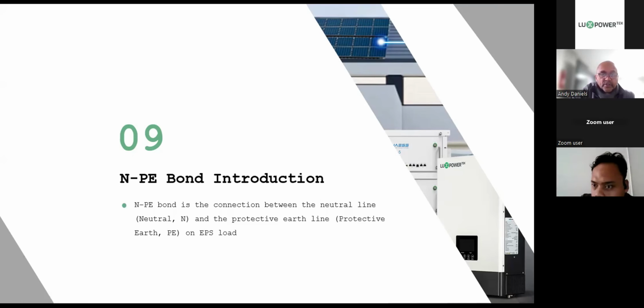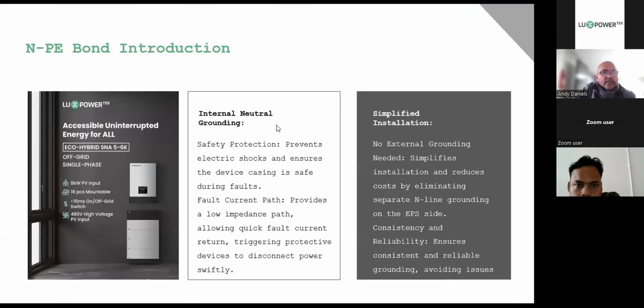You get a nasty little shock. Okay, but then we're going to look at this, which explains exactly what I've been talking about, and it's a safety protection, right? It ensures that the device's casing is safe during faults. There's a very, very low impedance fault current path, which allows, in the case of a short circuit, a quick return to your residual current device.